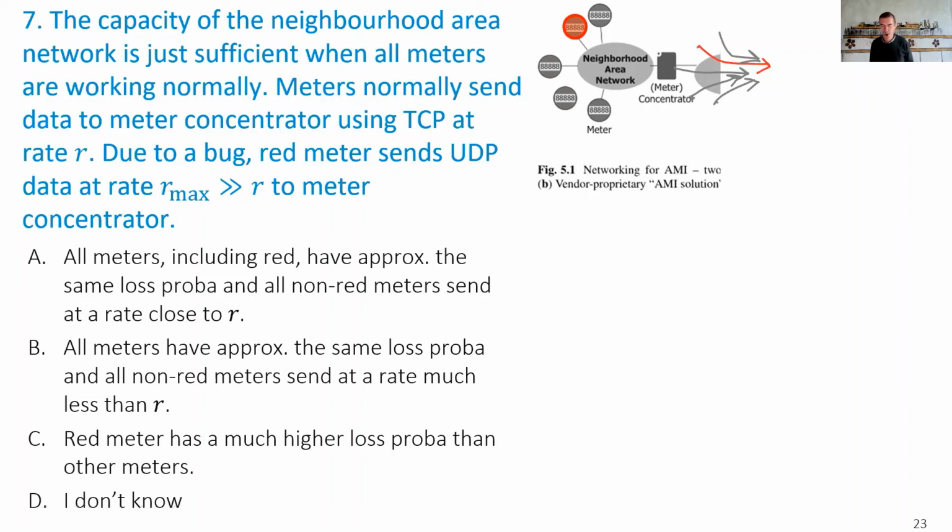This is one of the horror cases in substation automation, in industrial networks in general. If for whatever reason, a device sends much more traffic. That seems stupid, and why would a device do that? But computerized devices sometimes look stupid to human beings. And that can happen. For example, there is a programming error or an error in the hardware. There's a loop that's sending a message. And this loop, instead of saying, wait until you've received something, a signal here, then it blocks, keeps sending and sending and sending again.